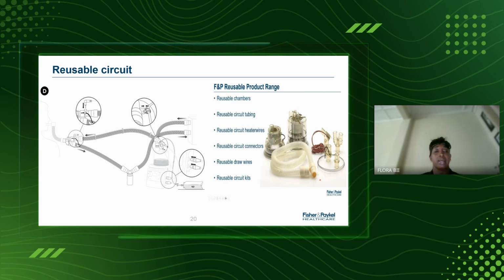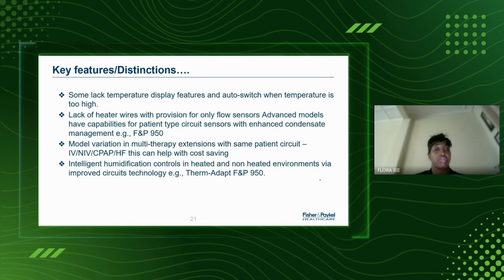The difference here being the inspiratory limb is the only limb that is heated. And the heater wires, though reusable, are actually drawn in manually into the circuit. However, it would comprise the water traps because the expiratory limb is not heated. So for the water traps, many times you would be required to discard the condensate from time to time, and that also marks a big difference between circuit technologies as well. So we do have these ranges where some would prefer using reusable circuits, while others would prefer the single-use circuits because of institutional preferences.